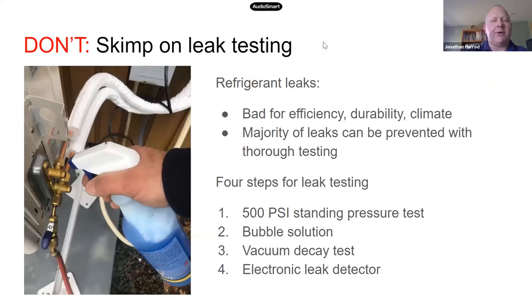For all the reasons I mentioned, we want to do everything we can to avoid refrigerant leaks. What we've reached consensus on is that there really needs to be four separate steps to your leak testing in order to eliminate the vast majority of these leaks. One of them is to fill the copper tubing that you've just installed with 500 PSI nitrogen and make sure that it holds that pressure.